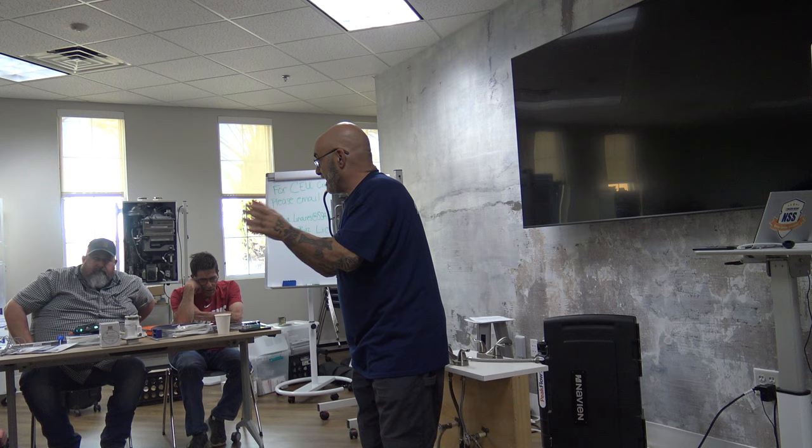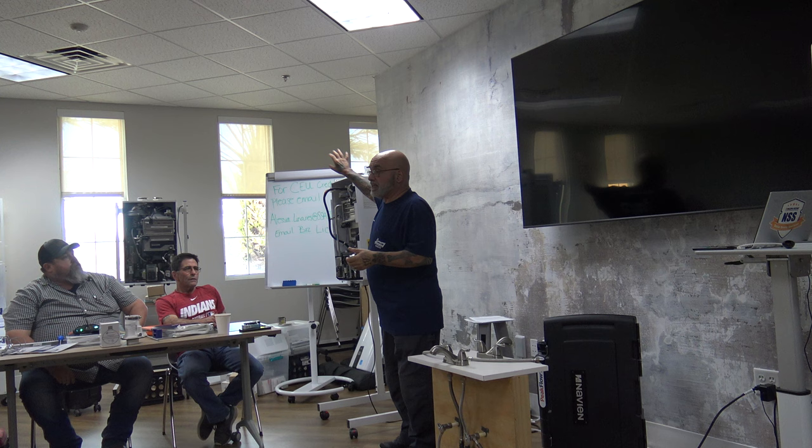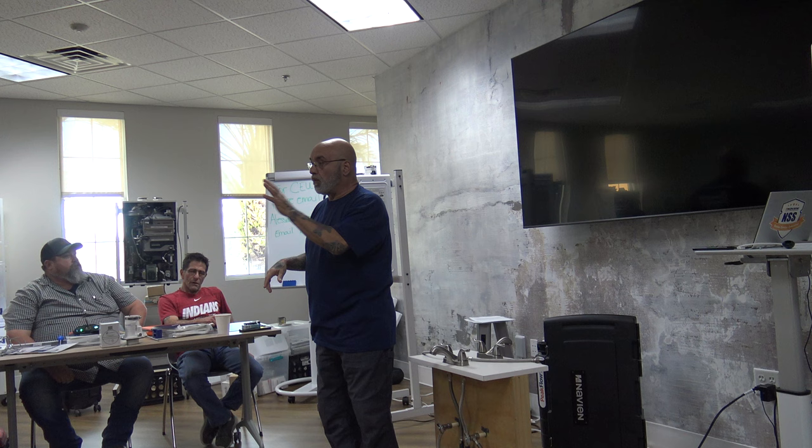Gotcha. Okay? Yep. Now, the other problem we see is they take this vent and they just bring it over to the B vent with a Fernco coupler. You can sleeve it, but we remove the B vent. We don't use a Fernco. You can buy a poly adapter that actually molds with lead around the penetration, with stainless steel screws and bolt, and it becomes watertight.